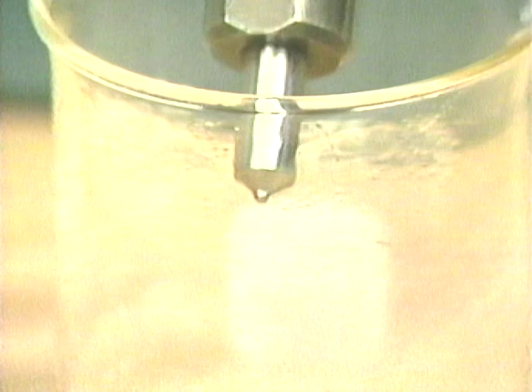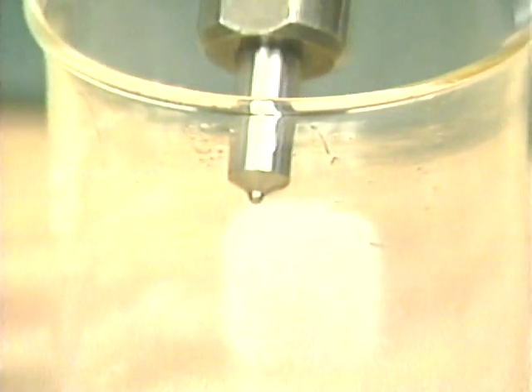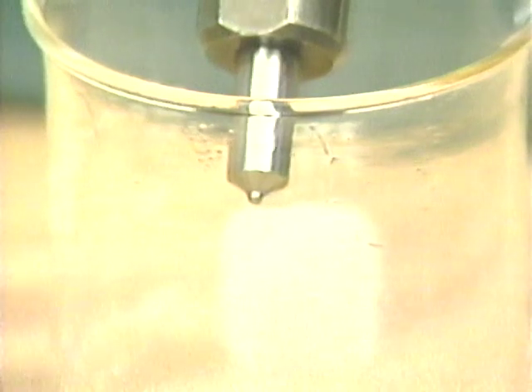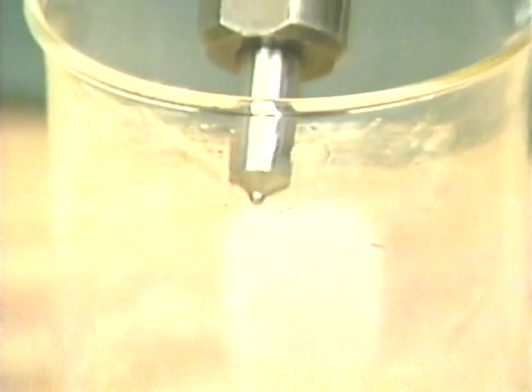The spray from each hole should be well atomized. All 4 sprays must be similar in shape. They should be spaced at approximately right angles to each other in a horizontal plane. Each spray should be shaped like a cone and spread into a 2-inch diameter circle at a distance of 6 inches from the nozzle tip.